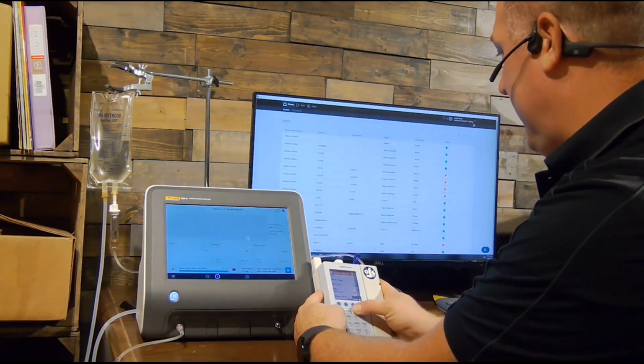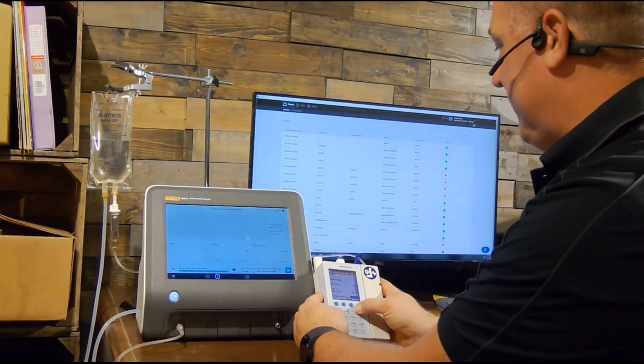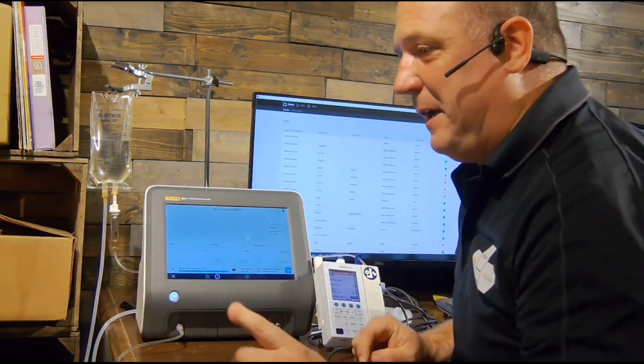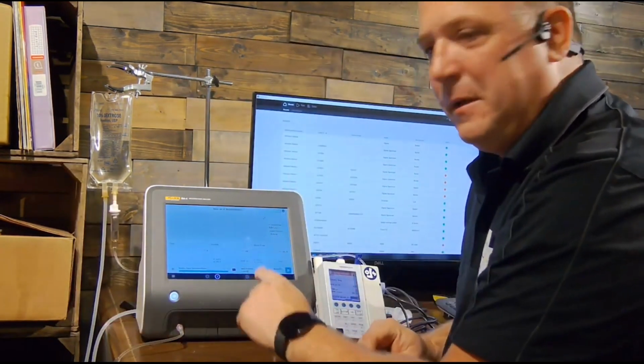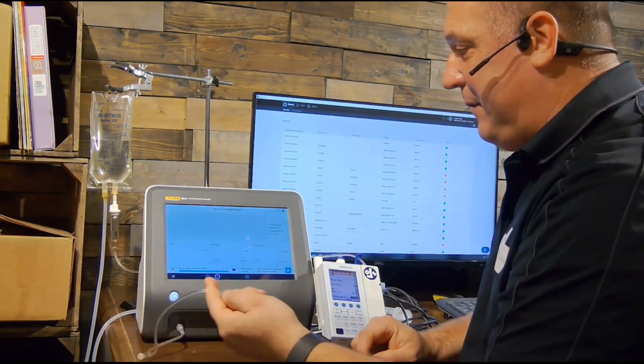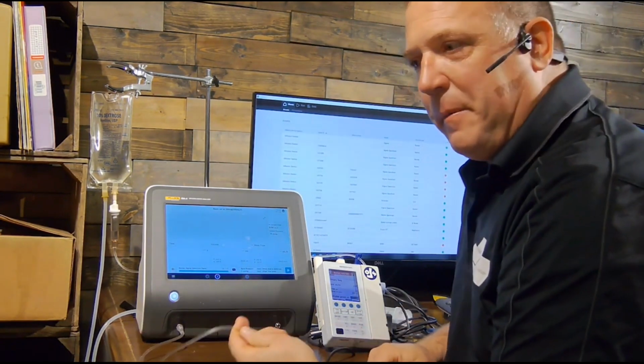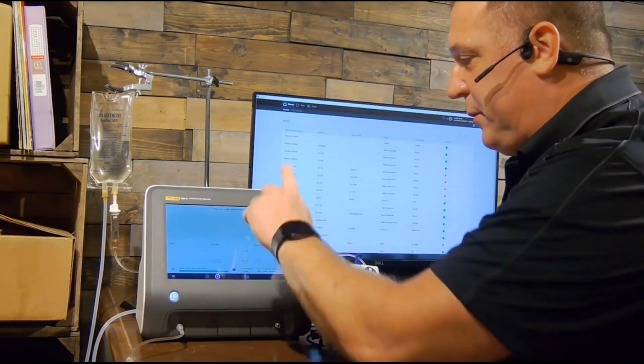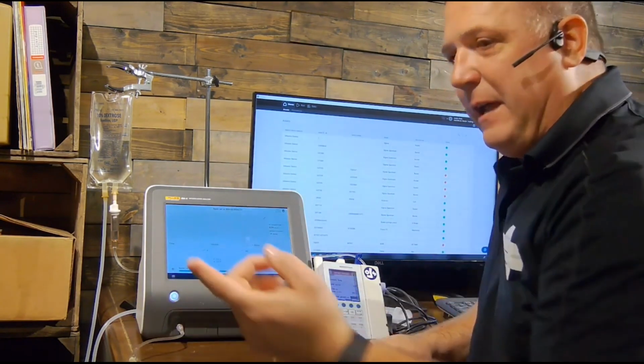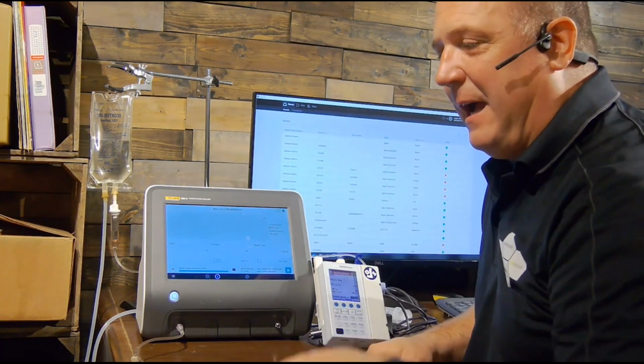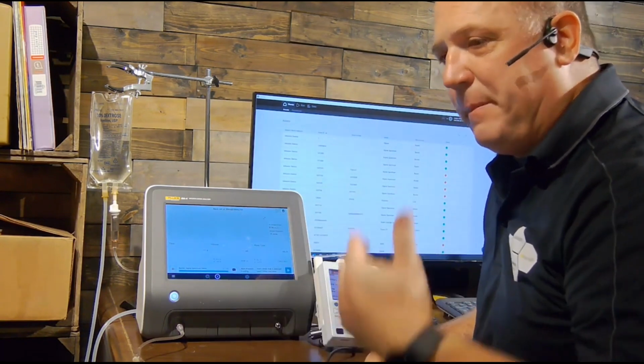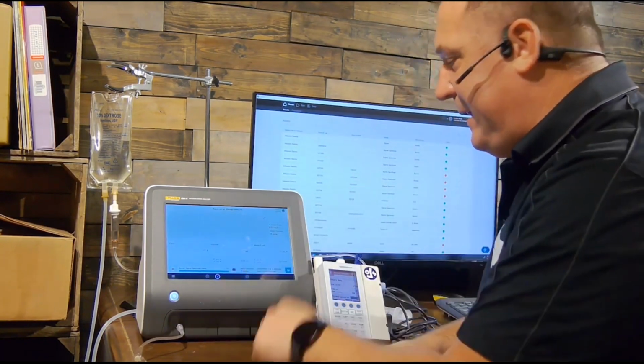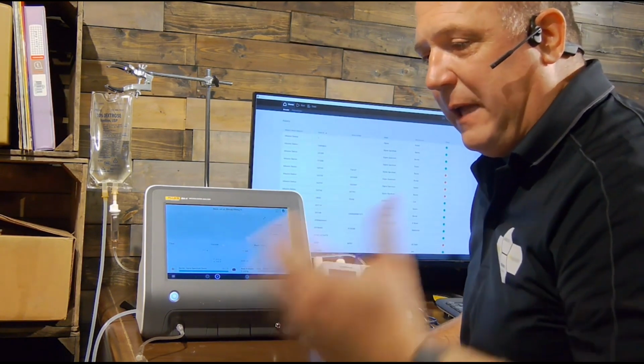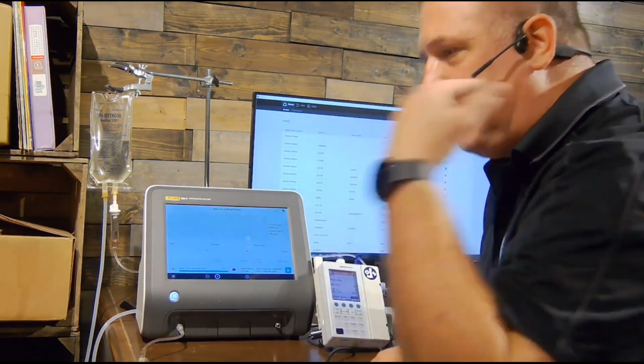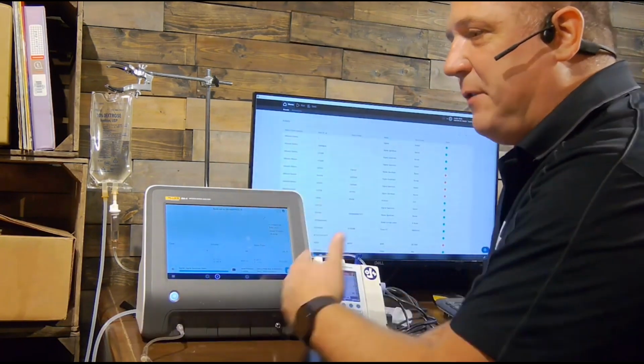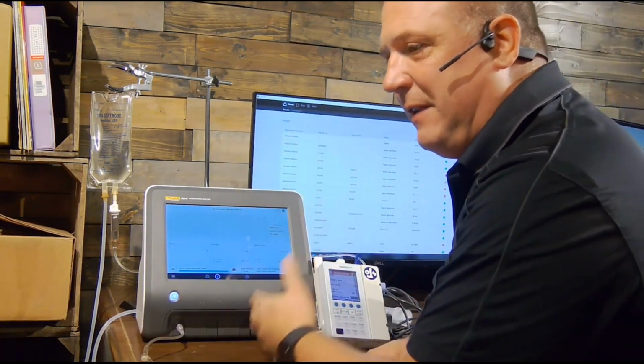Volume given, okay. All right, so my infusion pump is set up. Now you notice something here—I didn't have to prime the system. The reason is since this uses a piston-driven stepper motor, once I pushed all the fluid through here, there's no more air bubbles, so I only had to prime one time. It's not like the IDA-5 or the 4, where I used to lose my prime in between each of the tests. I already did it. So some of those PMs, like the Alaris, where that's built in, you just let it do its thing, but you don't have to do that to satisfy the IDA-6's needs anymore.